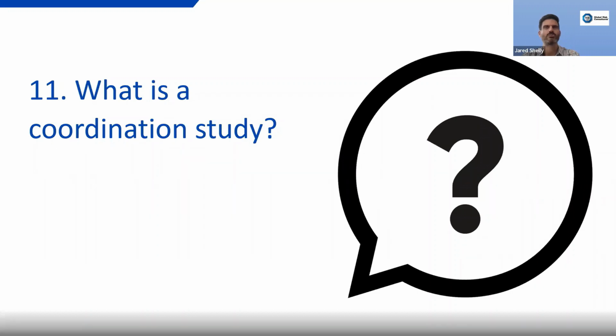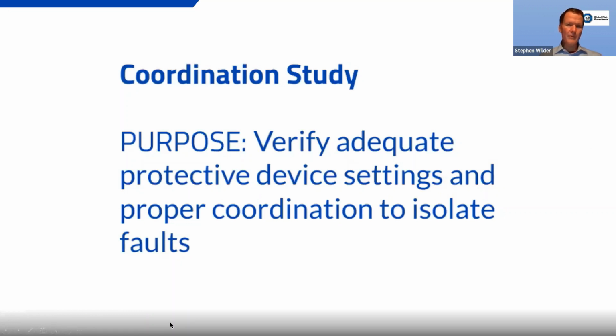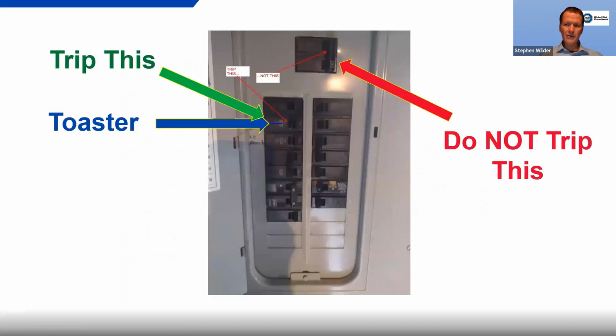So, Stephen, what is a coordination study? Well, in your house, you have a panel board. The panel has a main breaker. Let's say it's 100 amps. And there are branch breakers, say 20 amps, 30 amps. Let's say one of the 20 amp breakers feeds the kitchen receptacles. If your toaster has a short, you expect that 20 amp breaker feeding it to trip. Why doesn't the 100 amp main trip? Because the breakers are what we call coordinated. The breaker closest to the short circuit is the one that you want to trip. Otherwise, you'd lose power to your whole house. So the 100 amp breaker only trips if the 20 amp breaker fails to trip, or if there's a short in the panel board somewhere ahead of the 20 amp breaker.